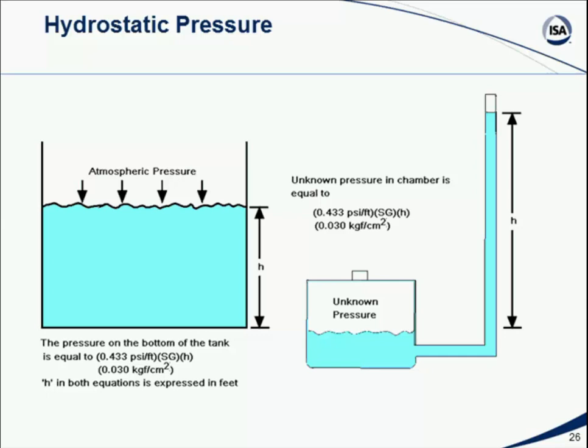So, of course, I can do the opposite. If I have the height, I can calculate the pressure. But if I have the pressure, I can, in reverse, calculate the height. And that's what hydrostatic tank gauging is all about. We take the pressure at the bottom of the tank and use that, knowing the specific gravity of the fluid, to compute what the height of the fluid in the tank must be.